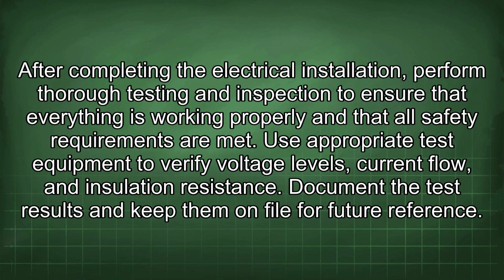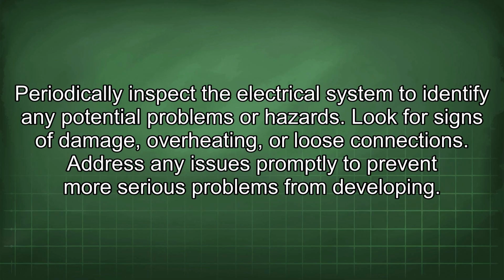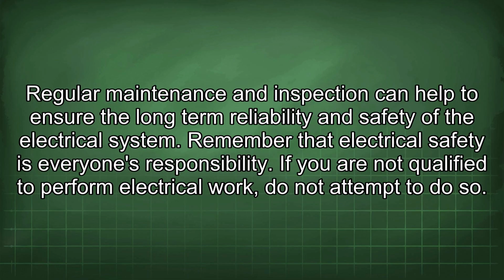After completing the electrical installation, perform thorough testing and inspection to ensure that everything is working properly and that all safety requirements are met. Use appropriate test equipment to verify voltage levels, current flow, and insulation resistance. Document the test results and keep them on file for future reference. Periodically inspect the electrical system to identify any potential problems or hazards. Look for signs of damage, overheating, or loose connections. Address any issues promptly to prevent more serious problems from developing. Regular maintenance and inspection can help to ensure the long-term reliability and safety of the electrical system.